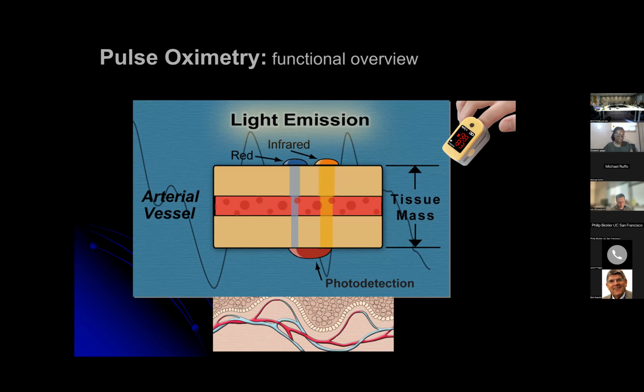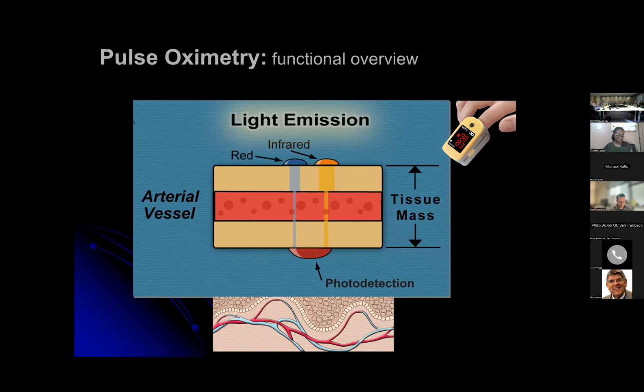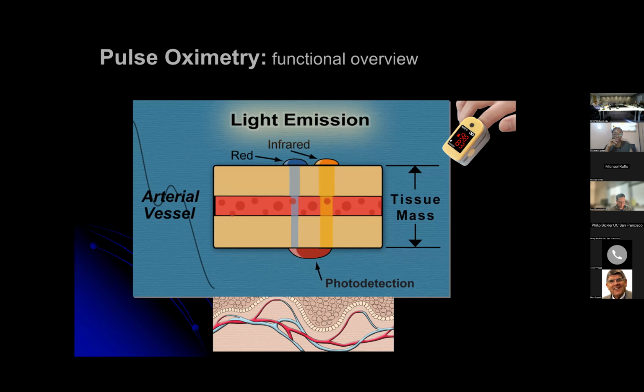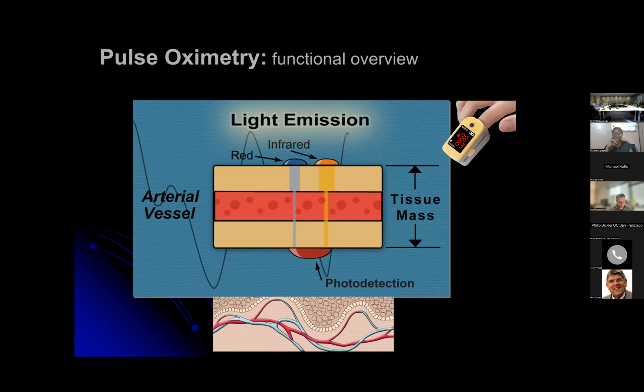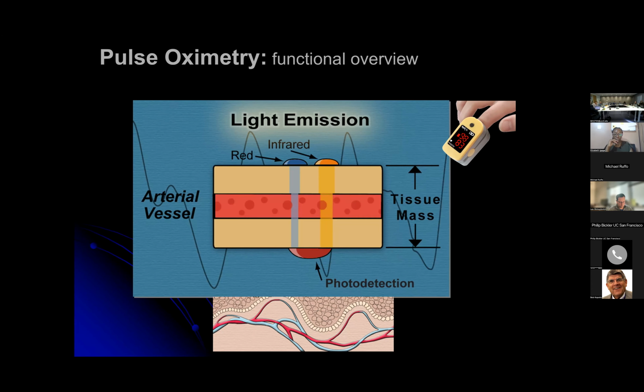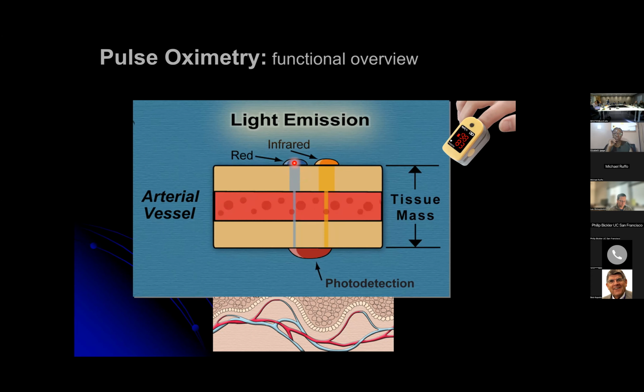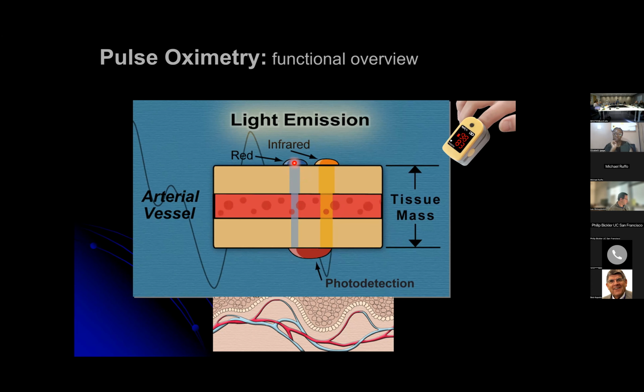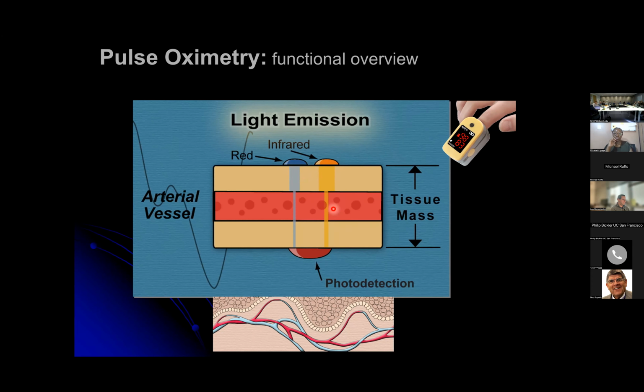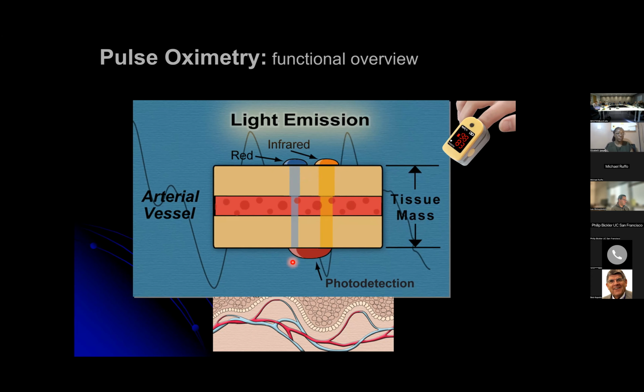So I bring that up because I want to make sure the audience appreciates why this indirect measure is really challenged by what some people have referred to as physio-optics, meaning there's physiology and there's light and the method of being able to detect that light. These are two light sources. One is red, and if you've seen a pulse oximeter in operation, that is the typical color you see as it's glowing over a finger or a nail bed. The other color is infrared, which is not visible to the human eye, but yet is there and is easily detected by this special detector.